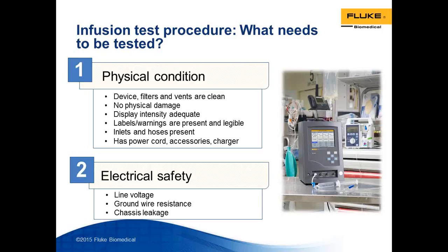This includes physical condition, which is looking at device filters. Is everything clean? Is there any physical damage? Is the display intensity okay? Are all the label warnings present? The inlets and hoses, are they present? Are they damaged? Power cord, etc. The second part is electrical safety, to make sure that the infusion pump does not pose a risk to the patient in terms of electrical leakage current. So in that case, along with leakage current, you're also looking for line voltage, ground wire resistance, and chassis leakage.